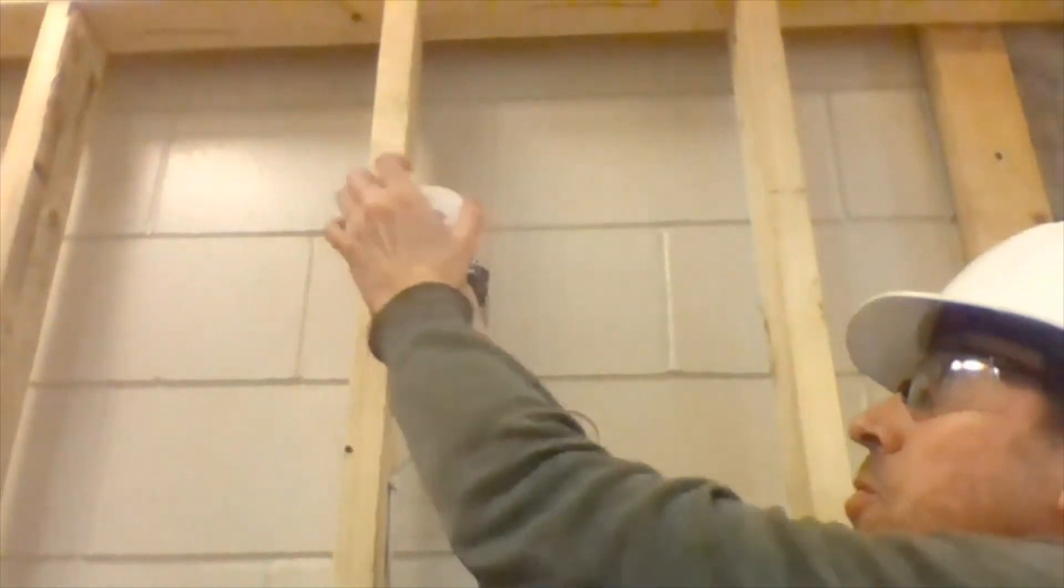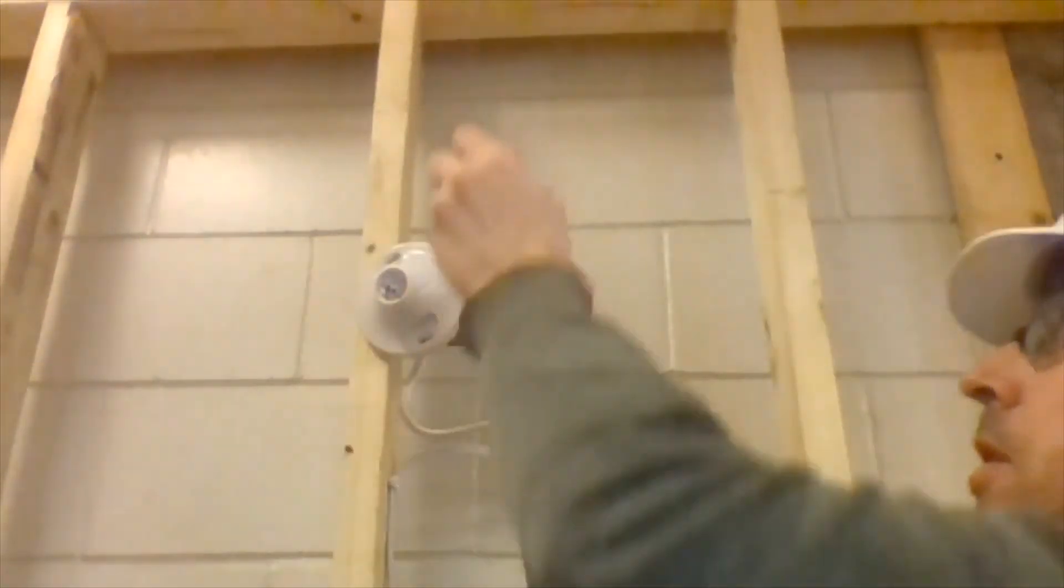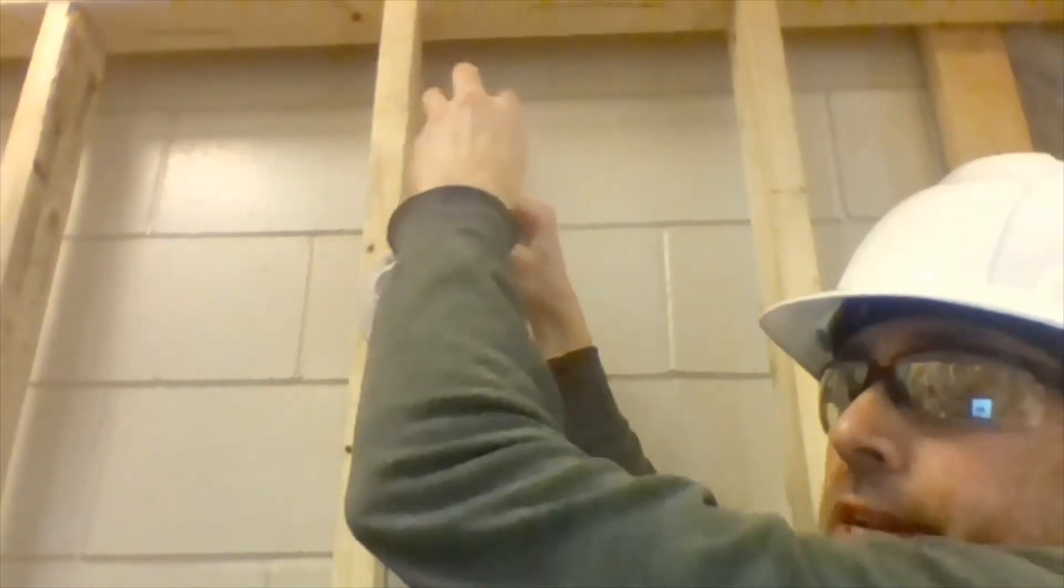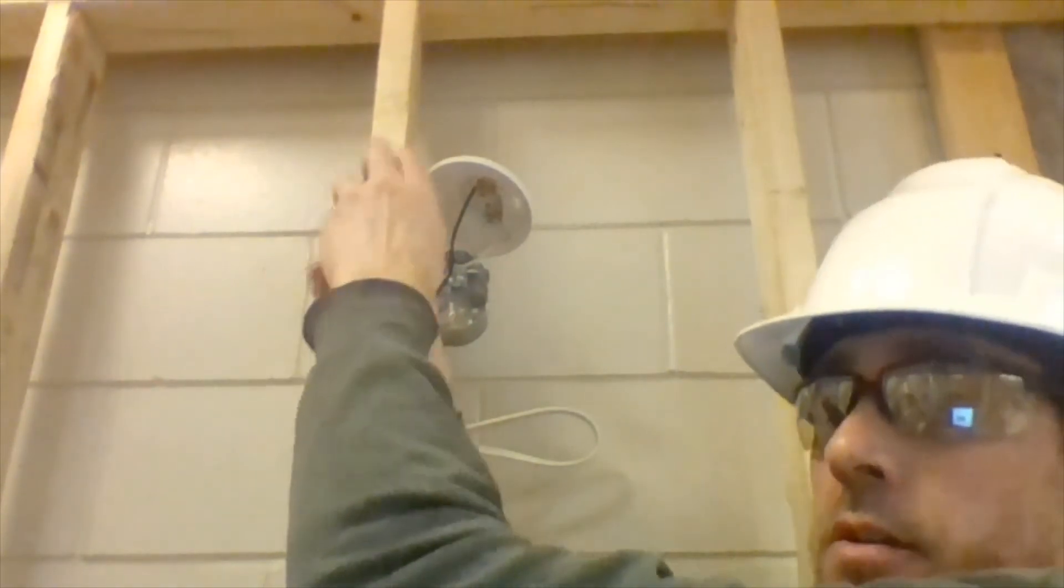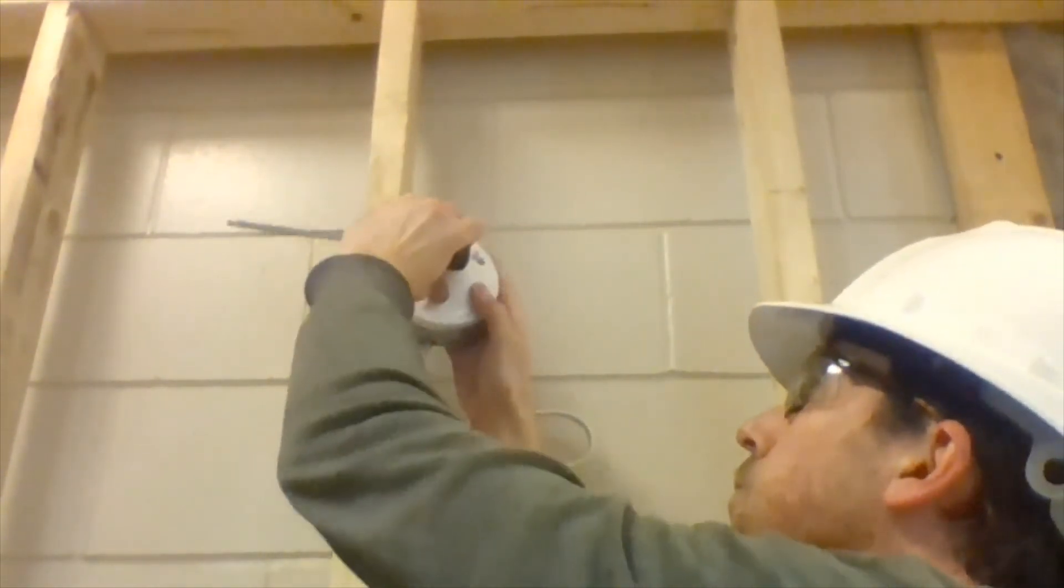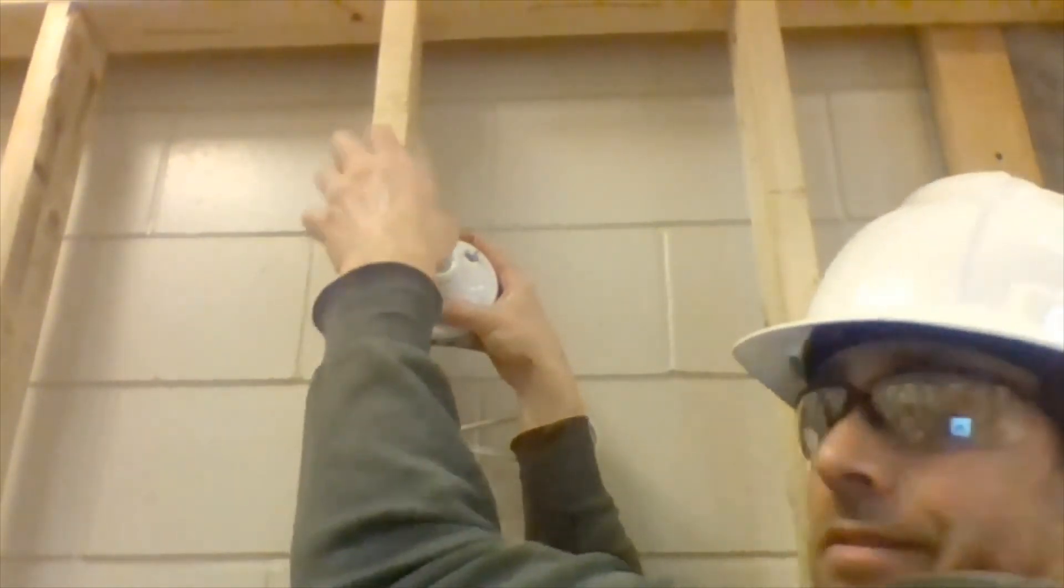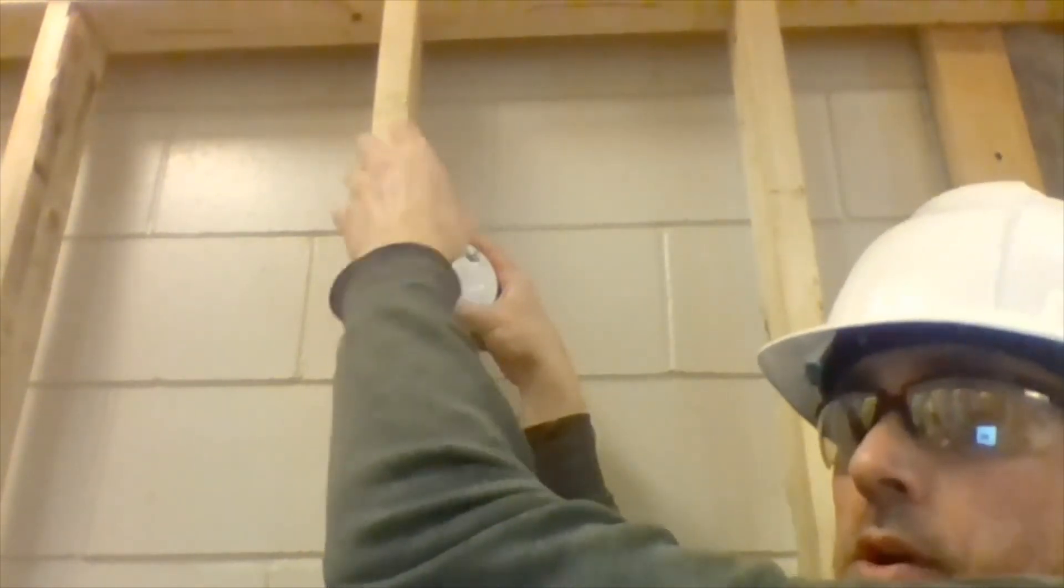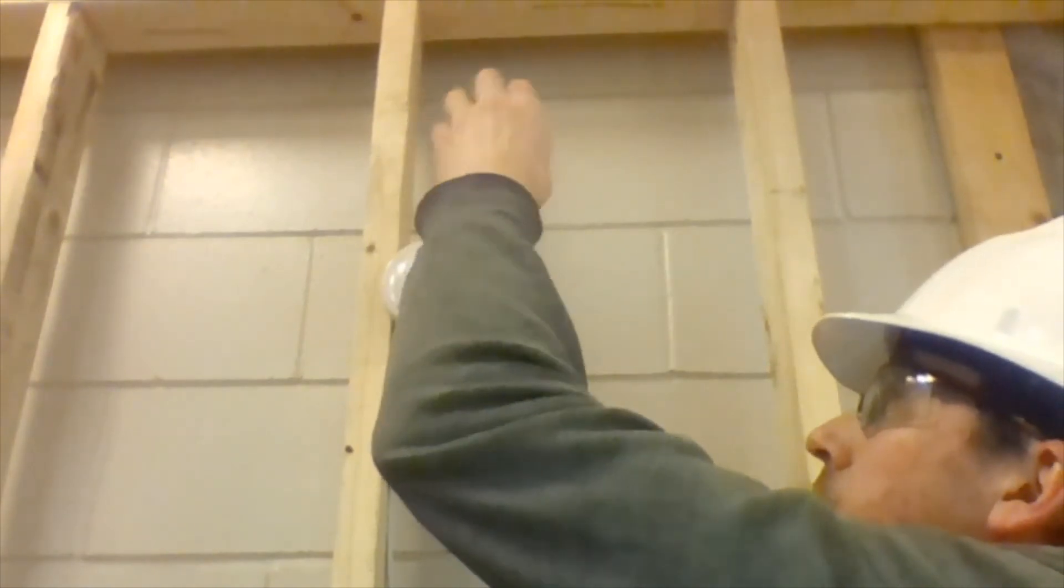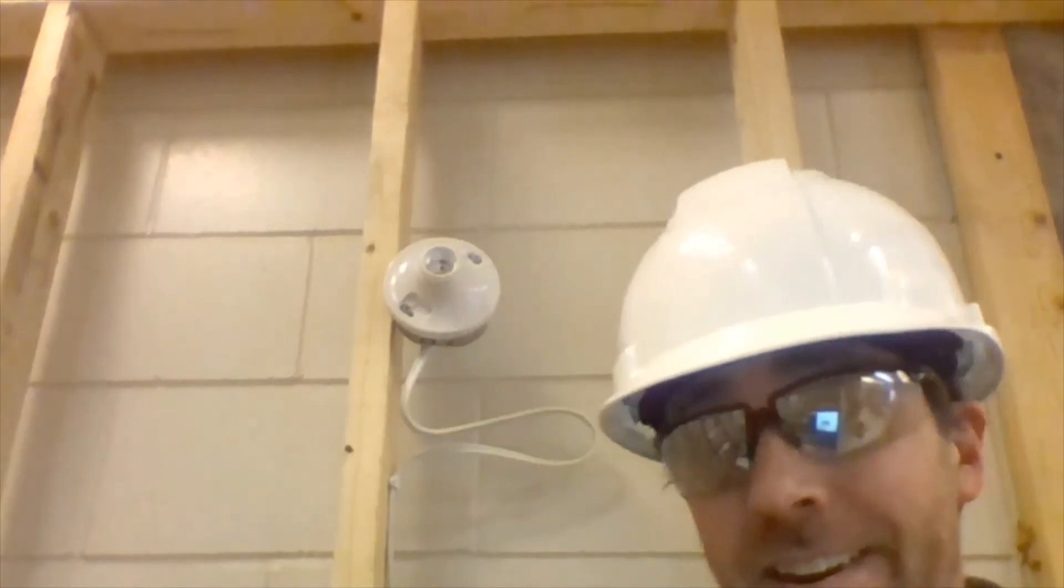At that stage now, we'll pinch the wires. And I'm going to fold them nicely into the box. And I'll have to loosen off these screws on the ends here. Because these are going to fit into our keyless lamp holder. These keyless lamp holders are made out of really cheap, junky plastic. Don't over tighten them. You'll crack them. And then you're just going to have to do this whole process over again. These kind of saddle. Kind of halfway in between here. It sort of doesn't look like it's supposed to. But they do sit sort of in between the larger part and the smaller part. And it's mostly just how they sit in the octagon box. And how's that?